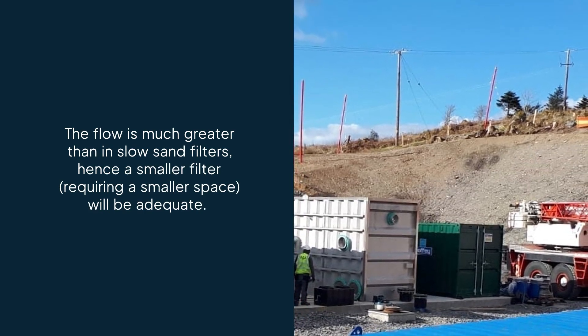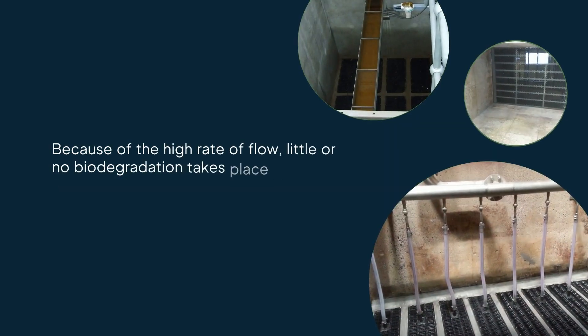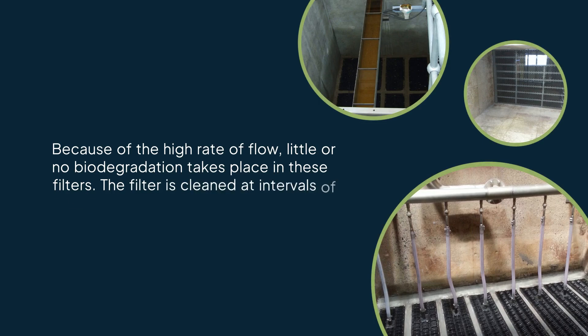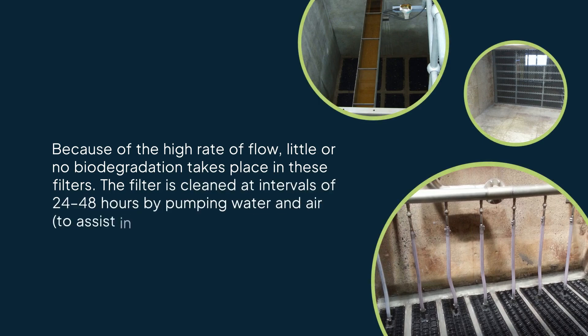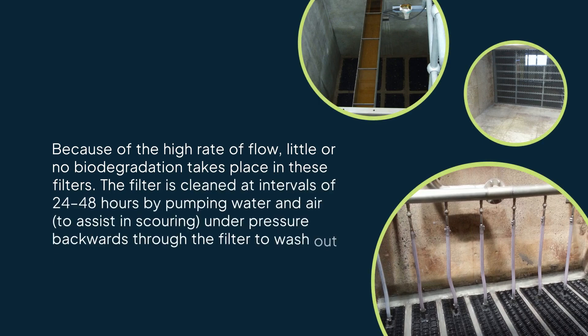Because of the high rate of flow, little or no biodegradation takes place in these filters. The filter is cleaned at intervals of 24 to 48 hours by pumping water and air under pressure backwards through the filter to wash out the trapped impurities.